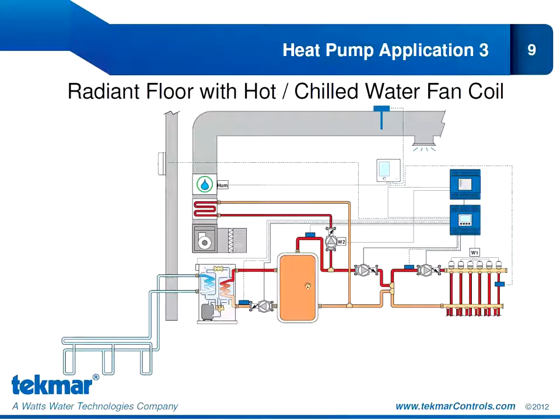When we switch over to cool mode, and this tank is now filled with chilled water, our fan coil is going to provide a first stage of cooling. We have the option here of doing radiant floor cooling, which has been getting a lot of attention in our industry lately. And controls like the 557 and the 406 have advanced features to properly, successfully execute radiant floor cooling, as we will learn when we discuss the functions of the 557 in greater detail.